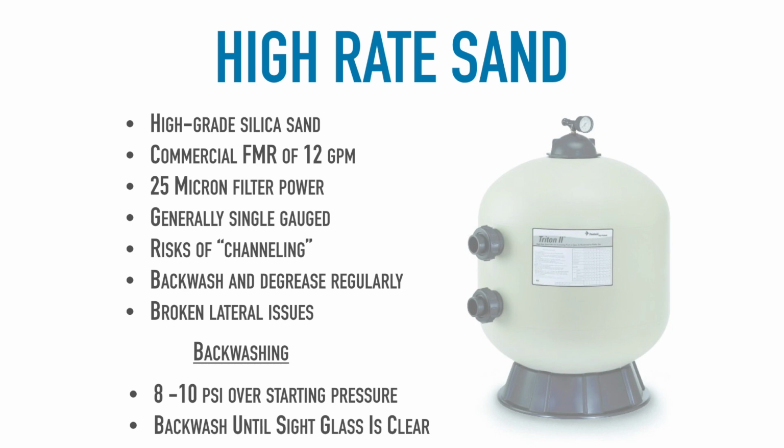Now, one of the big things that I will say is make sure that you're backwashing and degreasing once a month. Degrease once a month and backwash whenever you need to, whenever you see that 8 to 10 psi. Because if you don't, what's going to happen over time? Let's just say it's completely against my principles to backwash. I think it's a bad idea. Well, what's going to happen to my filter? Over time, I'm going to basically create a giant ball inside of that filter itself. That sand is going to compact in on itself. The grease is going to glue that sand together.